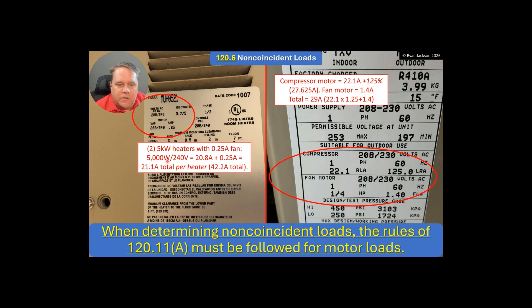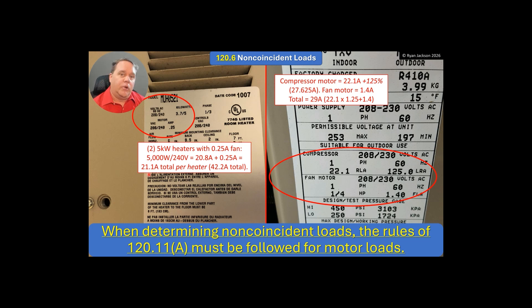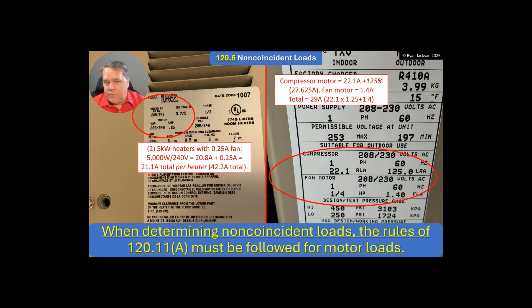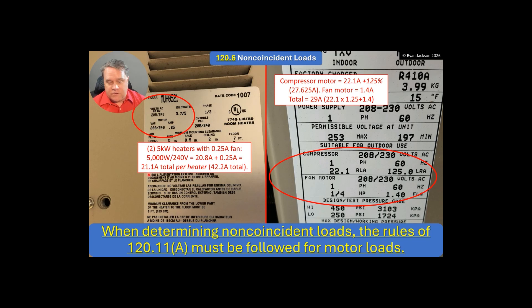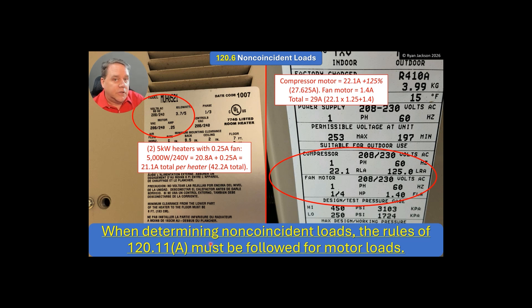So we've got 5,000 divided by 240, which is 20.8 amps. We're going to add the motor, which is a quarter of one ampere, so I've got 21.1 amps per heater. But there's two of them on the feeder, so on this feeder circuit I've got 42 amps of heat and 29 amps of cooling. If those are not going to be on at the same time, then I get to remove the cooling load. There could be instances where both are on at the same time — it's not just a hard and fast rule that you get to remove the smallest of the heating and air conditioning. Usually you can, but not always. So when determining non-coincident loads, you've got to follow the motor rules like we just talked about.